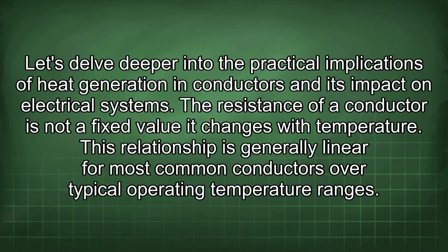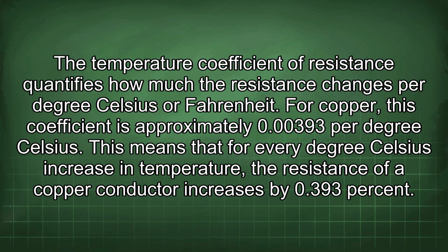Let's delve deeper into the practical implications of heat generation in conductors and its impact on electrical systems. The resistance of a conductor is not a fixed value, it changes with temperature. This relationship is generally linear for most common conductors over typical operating temperature ranges. The temperature coefficient of resistance quantifies how much the resistance changes per degree Celsius or Fahrenheit. For copper, this coefficient is approximately 0.00393 per degree Celsius.